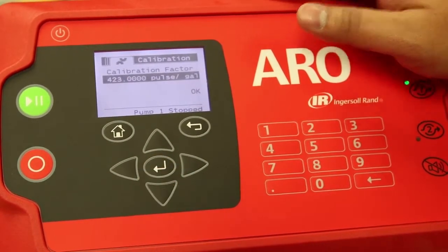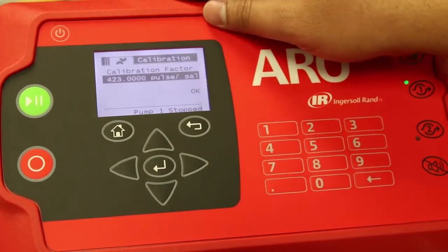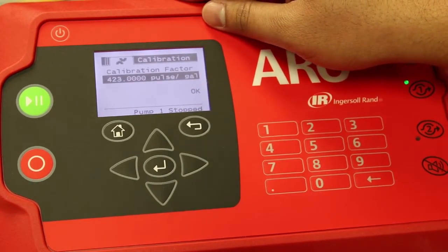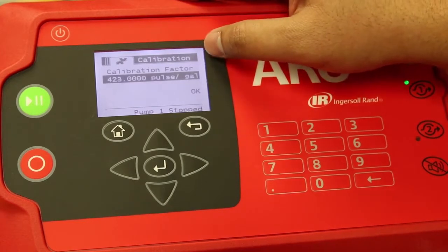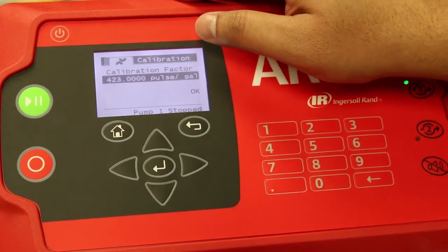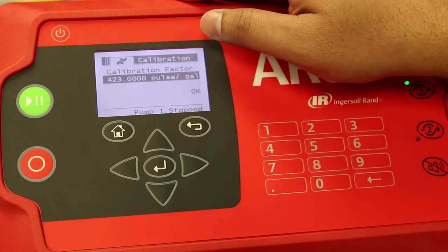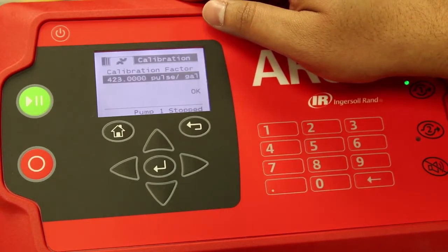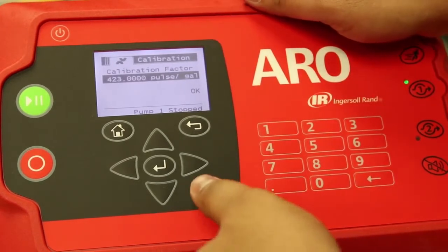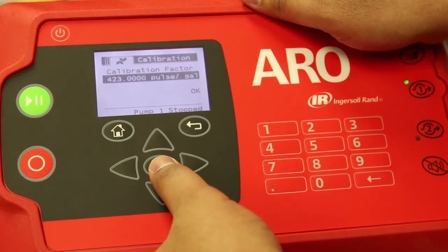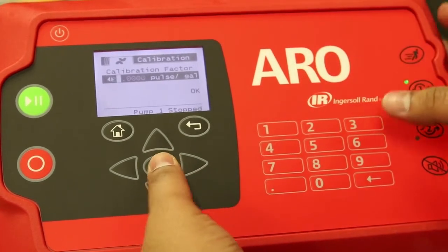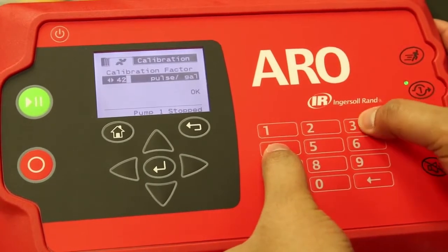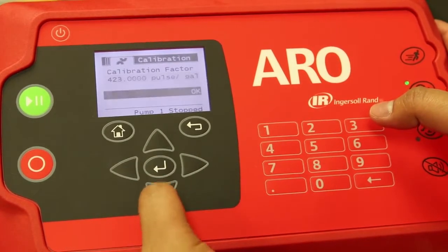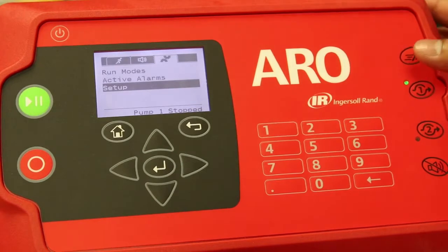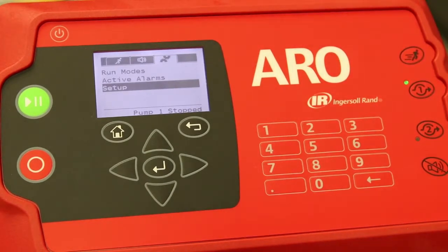Once we enter the manual calibration menu, the controller wants to see a calibration factor in the units of pulses per gallon. Most manufacturers of flow meters provide the calibration factor, or a K factor. In our case, it happens to be 423 pulses per US gallon, and we will enter that and hit OK. So that completes the manual calibration of the flow meter.